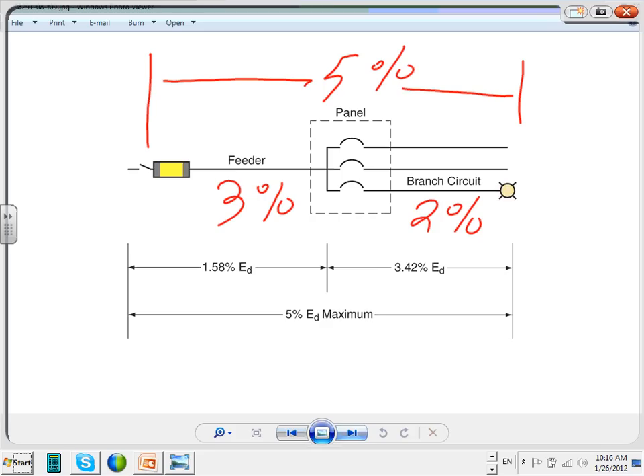The practice, guys, when you have voltage drop, is to maintain 3 and 2, or 2 and 3. The industry practice is you allow no more than 3% on the feeders because they're long, and the branch circuit is 2. What does voltage drop mean? Meaning if I started with a voltage right here of 480, I'm allowed at this load to lose 5% of 480. So let's take 0.95 times 480. I'm allowed to bring this one to 456 volts. This is 5% off 480, right?